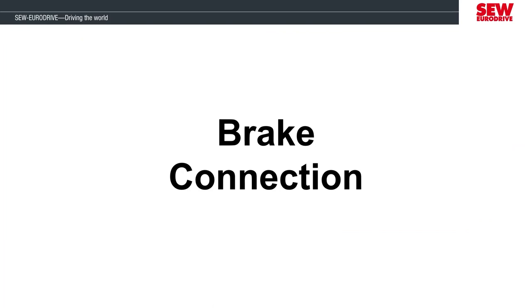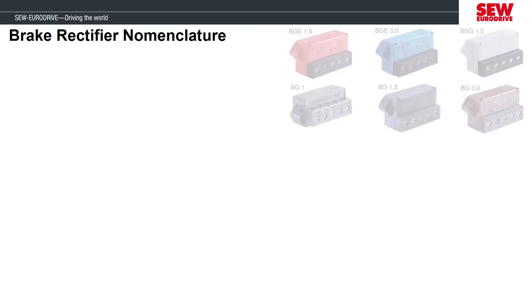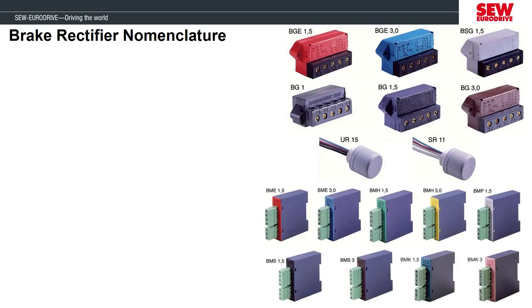Let's switch to discussing the brakes and rectifiers we offer for our motors and how the electrical circuit can be connected. If you use any of our brakes with a rated voltage greater than 24 volts, you will need some type of rectifier to control it. The rectifier can be located in the conduit box of the motor directly beside the motor terminals, or it can be located in the electrical cabinet snapping to a DIN rail — common when an inverter is controlling the motor or when it's easier to have the rectifier closer to the voltage contactors.